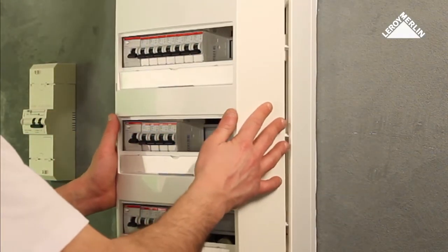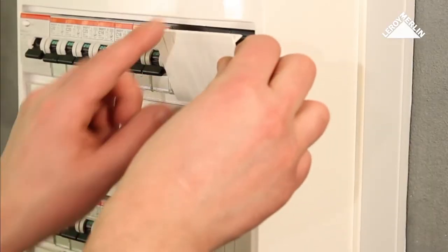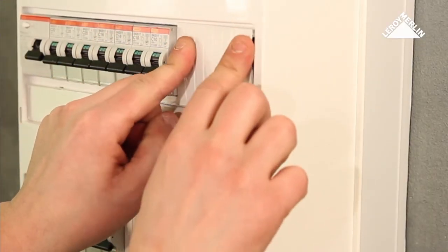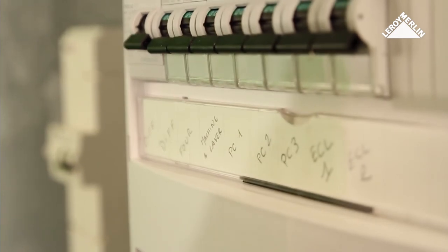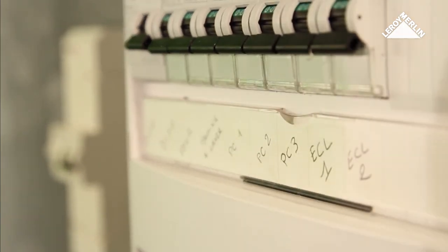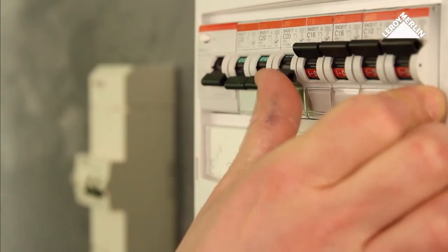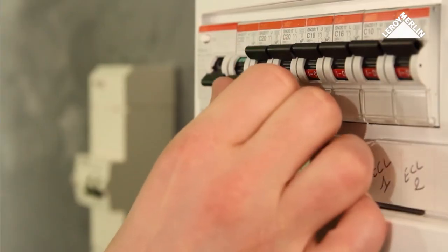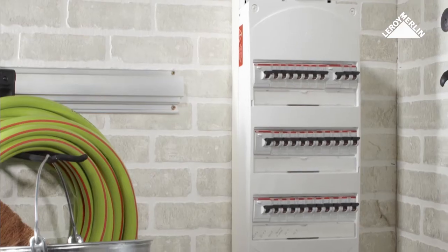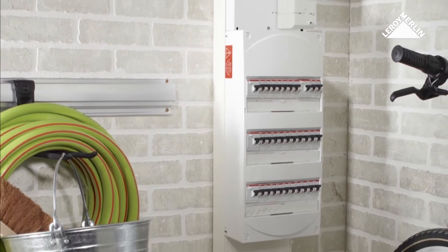Replace the distribution board cover and insert blanking plates to cover any empty spaces. Label each of the RCD modules. All you need to do now is to reconnect the power and turn on each of the individual RCD switches. Your home is now safer with a new distribution board.